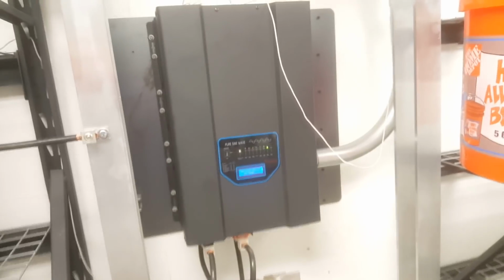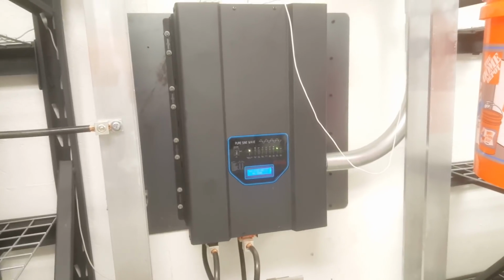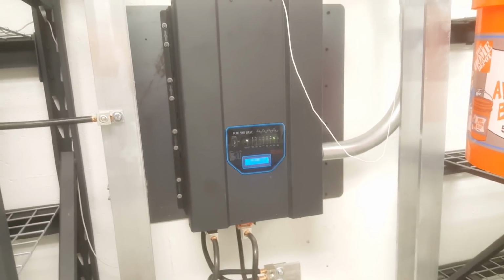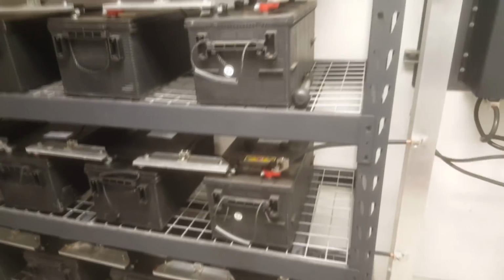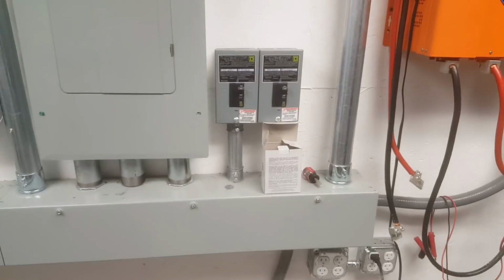And from there, it goes back through this same liquid tight into this other breaker, and then runs through this EMT back over to this battery charger, and this battery charger takes that 240 volt single phase and converts it to 48 volts DC or so, approximately, to charge the batteries. I use that on rainy days or when I need extra power to power things. So that's what those are for.